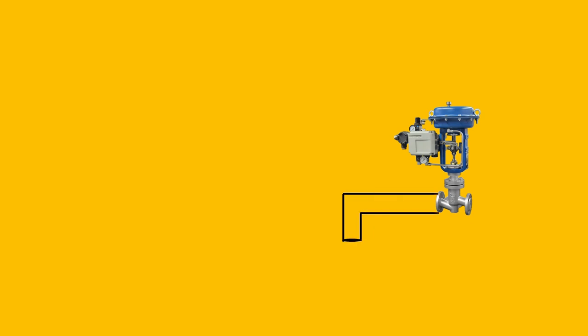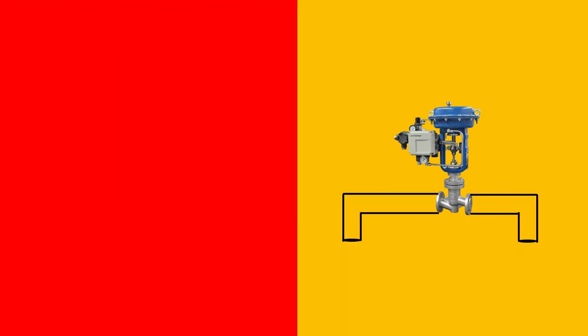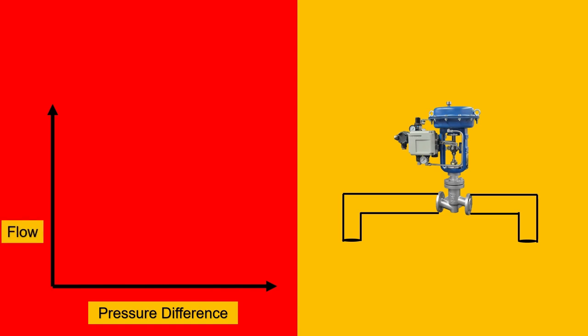Here imagine that this is my valve and I've connected it to a pipe and now I'll plot a graph between the pressure difference and the flow. So if you see here, when I keep the upstream pressure is 24 bar constant and the valve opening at around 50% and in the downstream, I keep it 20 bar, 19 bar, 18 bar. I keep reducing it. I'll get a very linear curve. This makes sense.